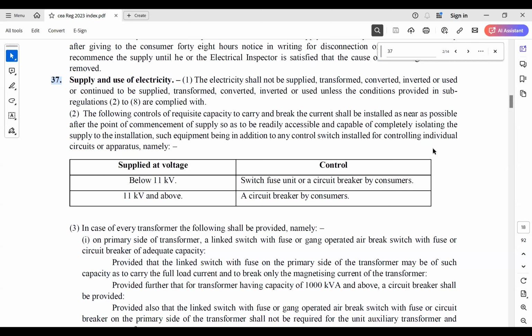is that when the transformer is located at the rear end of the factory, like sometimes DISCOM has a mandate that they should provide the metering near the gate. So many times what consumers do is that they provide the entire substation, like say HT meter, transformer, switchgear, breakers, everything near the gate. Sometimes that transformer is shifted behind, due to space limitations or whatsoever. In that case, what is happening is that near the point of supply, there is a breaker.